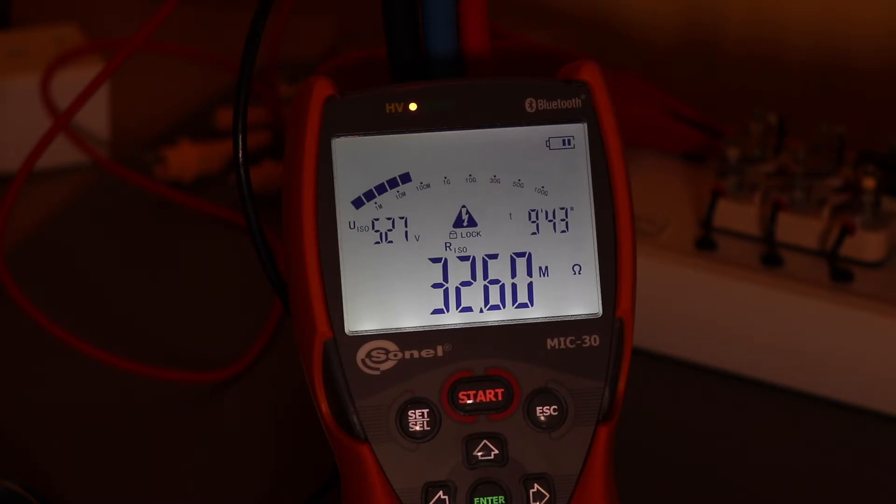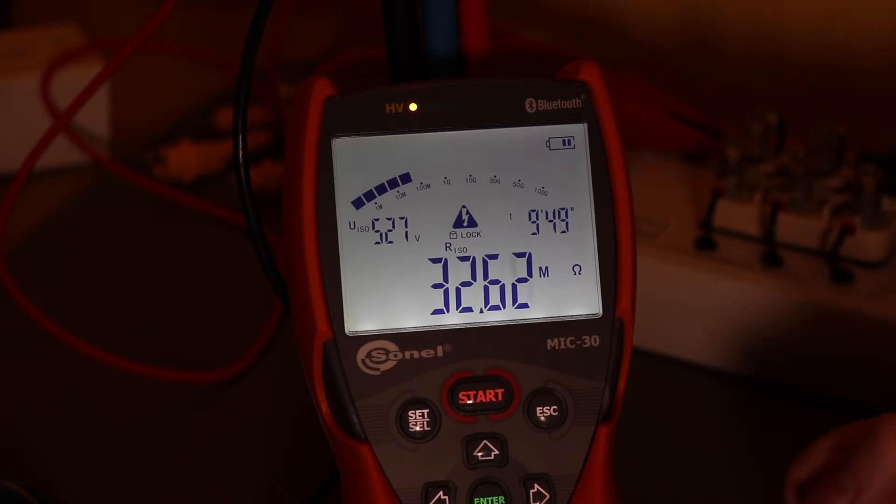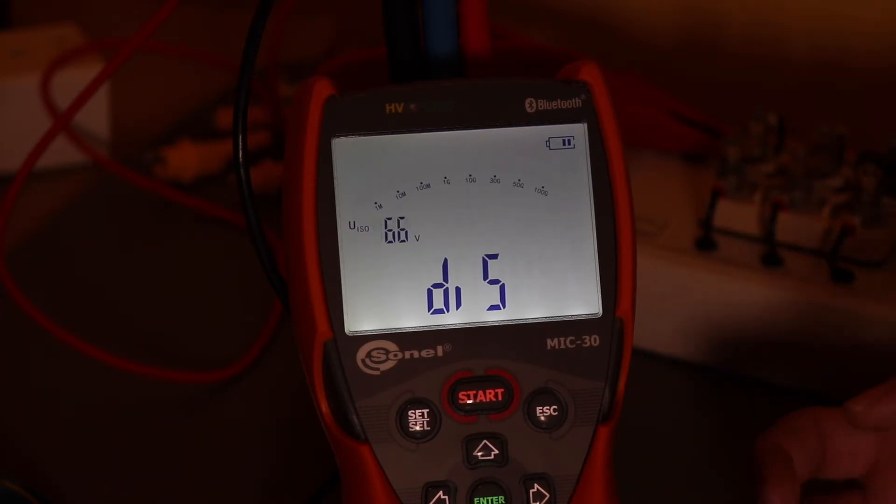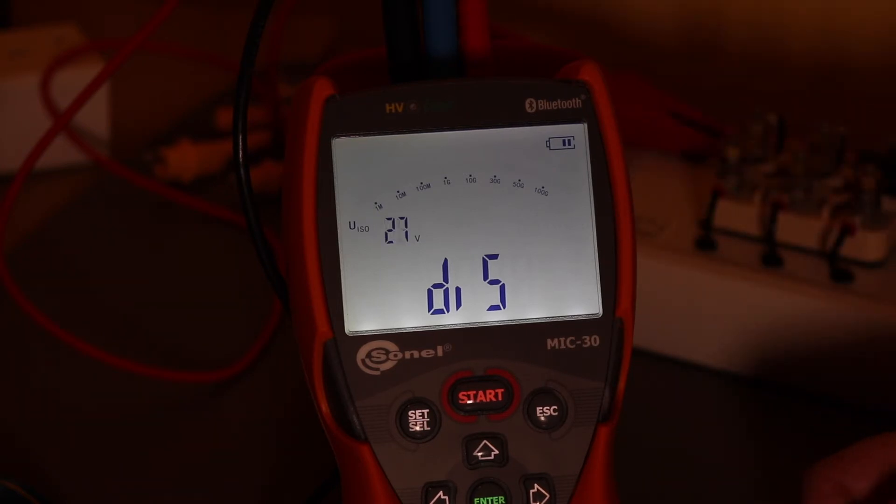And what I will do, this meter, as I do all the insulation testers these days, go into a discharge to get rid of any residual voltage after the test. And what this particular meter does is it will monitor that and it will go into alarm mode. So there's the final test. It's finished that. It's gone into a discharge. And in a few seconds time, it won't have discharged quickly enough. And it will move into a voltage detect mode.